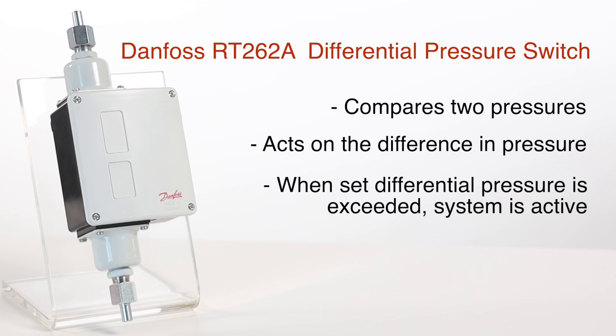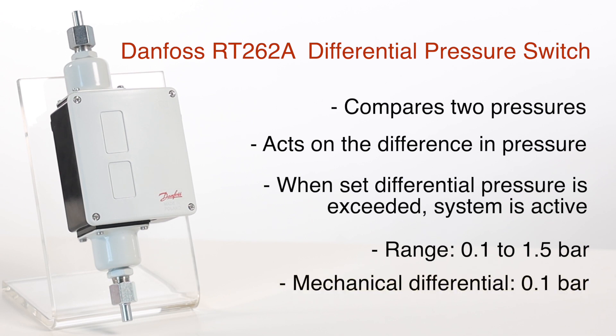In our example, we'll be demonstrating how to set up a Danfoss differential pressure switch for falling pressure applications. We've chosen an RT262A with a measuring range of 0.1 to 1.5 bar and a mechanical differential of 0.1 bar.